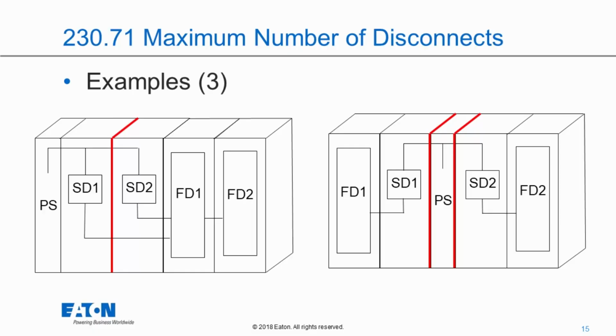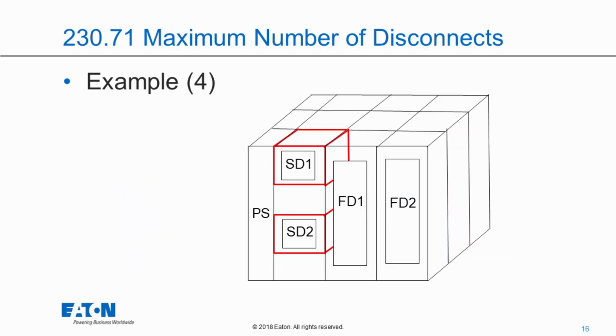And then on the second side, we have another example where we have basically the pull section in the middle, and then I branch off to each service disconnect. And again, full vertical barriers would be required. And the last condition would be for switchgear, and switchgear is very compartmentalized, so that is very easy to comply with. What you have here is a pull section, and then we have 2 service disconnects. Those would be via cross bus over to the, like SD1 would have cross bus supplying over to FD1, SD2 would have cross bus supplying over to FD2.